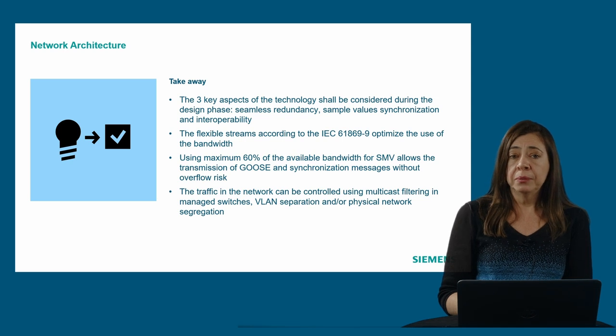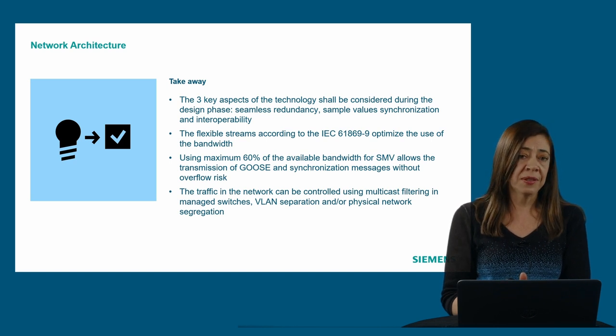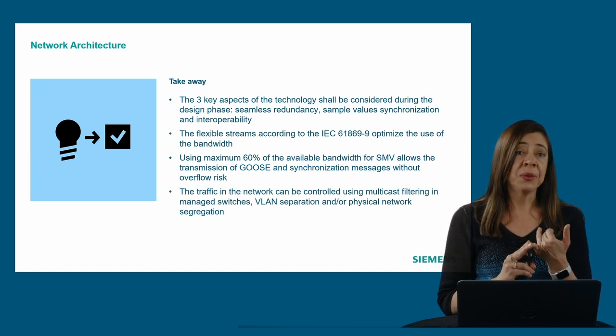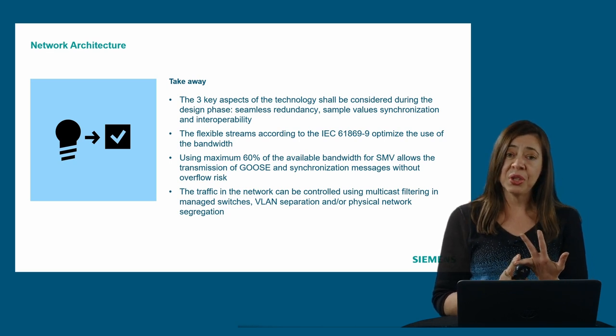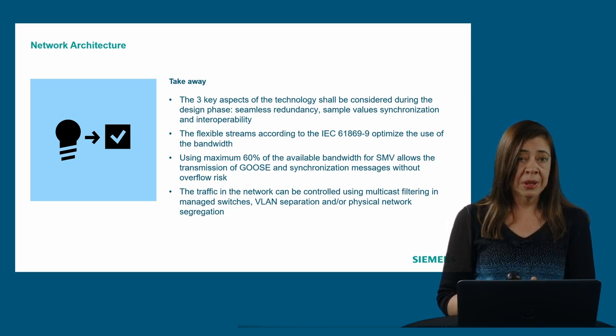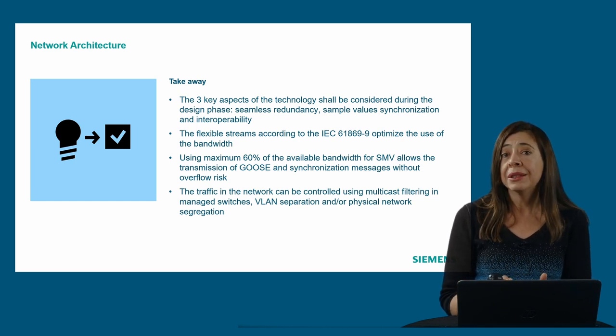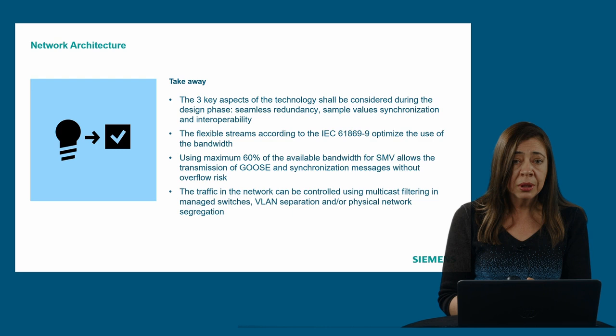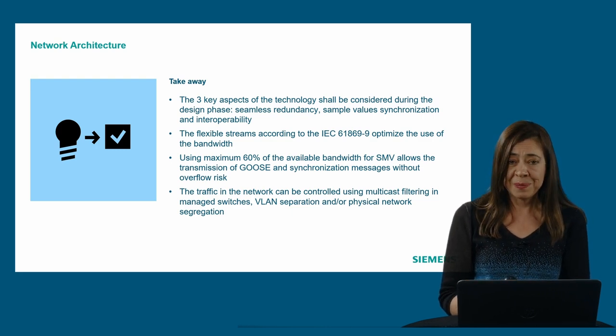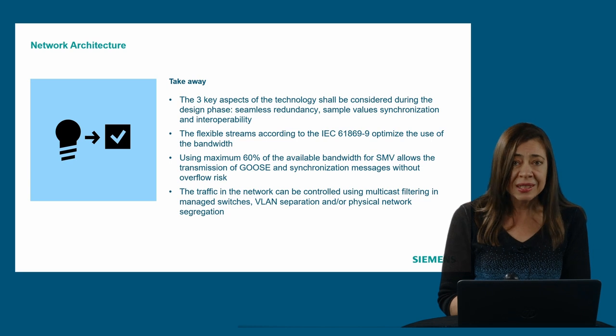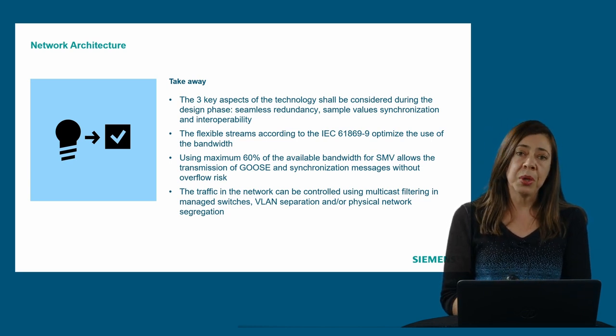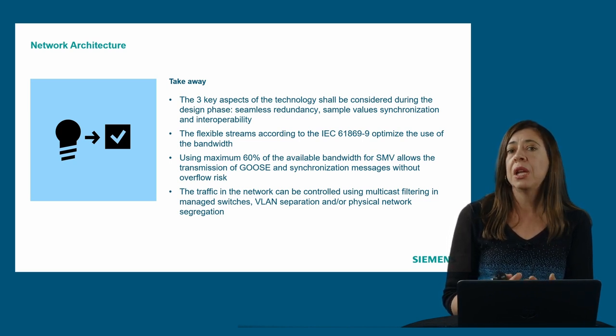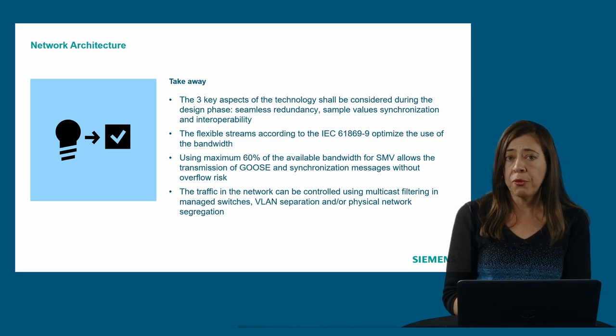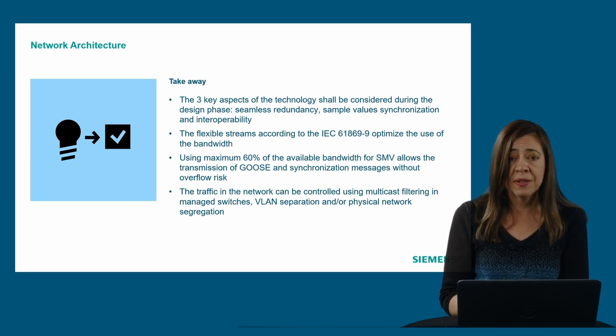So now, to take away, the three key aspects of the technology that shall be considered during the design phase are seamless redundancy, the sample value synchronization, and also the interoperability. The type of stream that you use will impact the use of the bandwidth in the network. That's why we recommend using flexible streams. A maximum of 60% of occupation of the bandwidth using sampled measured values should be considered, so you have enough bandwidth for other types of information such as GOOSE messages and synchronization messages as well.